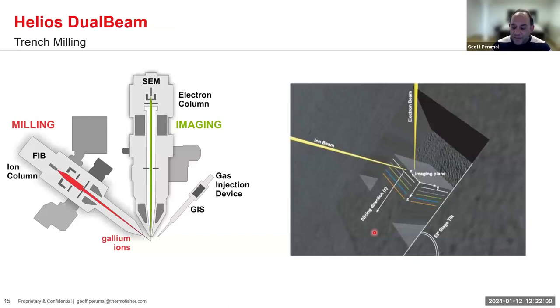For a focused ion beam, we actually introduce a second beam in addition to the E-column. The primary electron beam does all acquisition and imaging, meeting at a coincident point with the focused ion beam, which does the ablation. In the case of our tools, this coincident point is about 4 millimeters below the pole piece, allowing simultaneous ablation and acquisition without stage movements, which helps speed up acquisition.